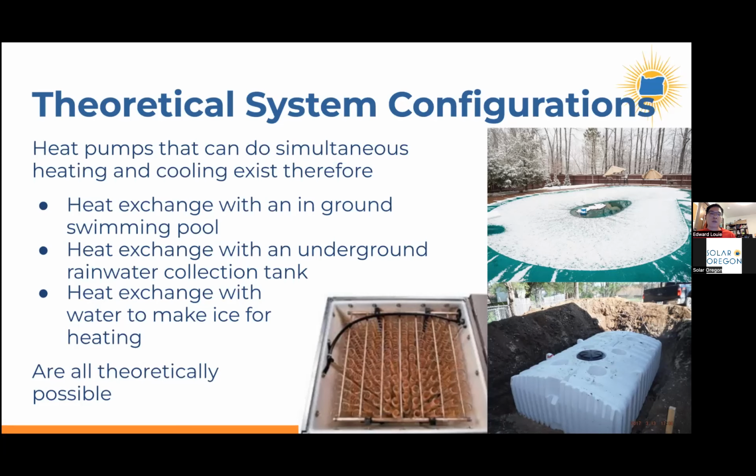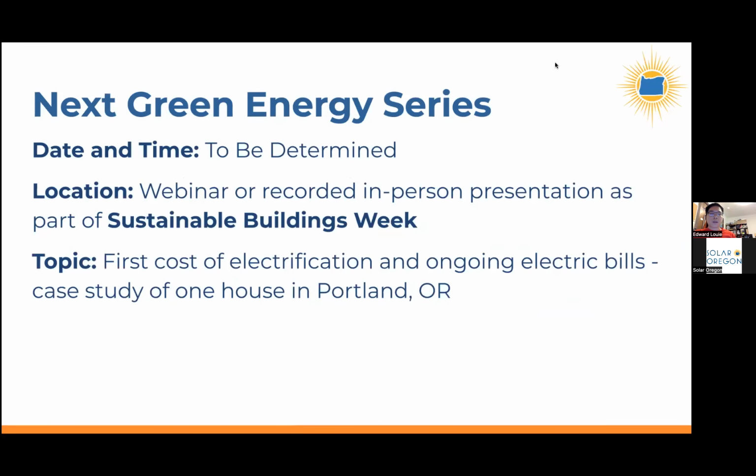So that's very easy to do, because a lot of heat pumps can work down to 5 Fahrenheit or negative Fahrenheit outdoor air temperatures and still extract heat from those sources. And then the refrigerant needs to get to minus 25, minus 30 Fahrenheit in order to do proper heat exchange with outdoor air that's 0 Fahrenheit. And so, of course, that takes a lot of energy to make a refrigerant that cold. And you need to run the outdoor fan and the outdoor unit at really high speeds in order to move enough air to extract heat out of such cold outdoor air. And so intuitively, a system like this would be much more efficient because it would be a lot easier to extract heat out of a 45, 40 degree or 38 degree source. So that is the story there.